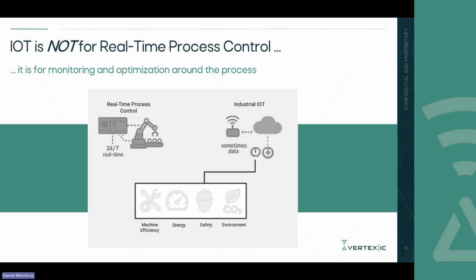Typically these sensors are battery operated and wirelessly connected, so they're not sending a signal every second. Usually signals are sent every 5, 15, 30, or 60 minutes, because they're battery operated. If we ran the sensor every single second, you'd be doing more maintenance than you're getting diagnostics from. So this is something I deploy to grab a snapshot of my health every so often.